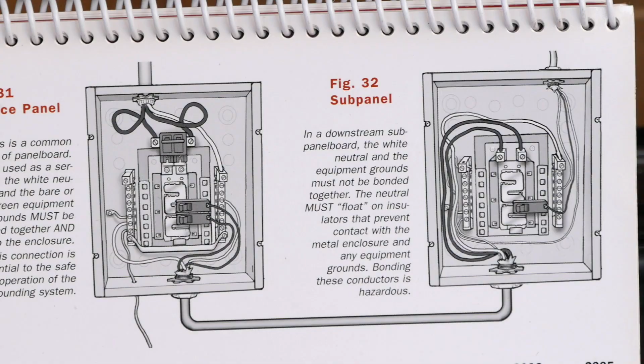Next, it's important to run your wires cleanly inside here, and also leave a little extra wire in case you need to rewire your box. Incidentally, this isn't my cleanest work, because I already rewired this box when I changed my mind between 30 amp 110 and 50 amp 240. But because I followed my own advice and ran my wires a bit long, it was easy to change over the breaker locations I needed to.